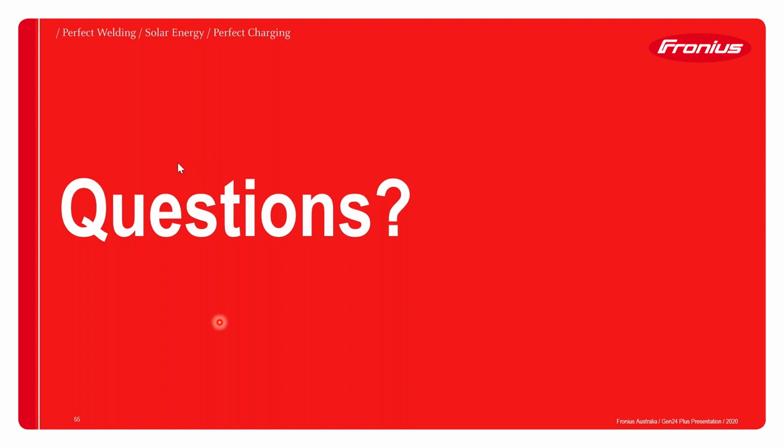Colin had a question about 15 kilowatts, three strings of 10.62 amps a string, on a three-phase inverter. Can I install a 10 kilowatt three-phase inverter? You can check that on our Fronius solar configurator, or you can use the OpenSolar design for this. Definitely, we can check that. If you can just send us an email, Colin, we can have a look.